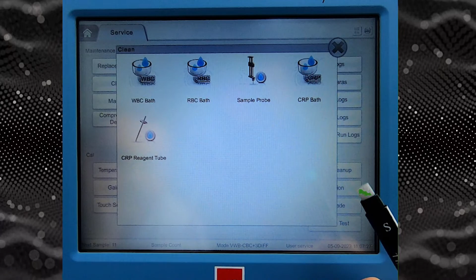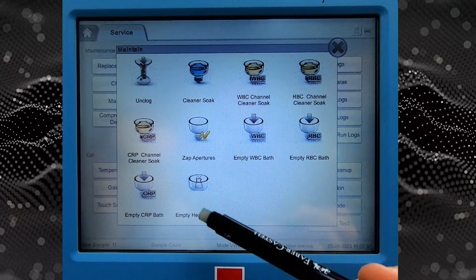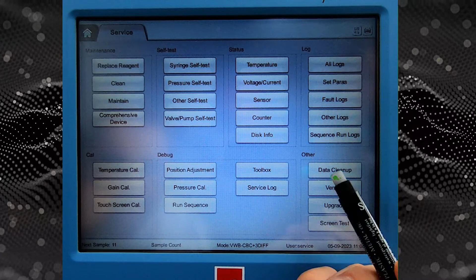Service. In the service, we can replace reagent, we can clean the analyzer, right? In the maintenance, we have like a cleanser, so unclog, and do other stuff, right? So I think this is pretty straightforward. Fluidic initialization. So this can be useful during the first installation of the analyzer. Prepare for shipment. So this is also useful when you plan to shut down the analyzer for a few weeks. I recommend to prepare it for shipment because the whole process will rinse the analyzer with deionized water and remove the residue of the reagents.